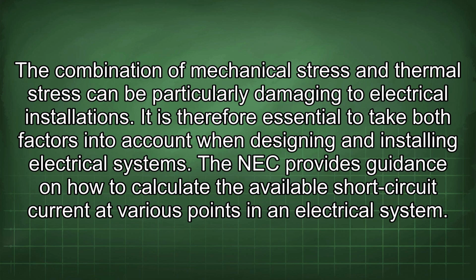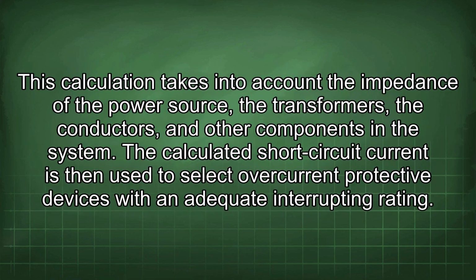The NEC provides guidance on how to calculate the available short-circuit current at various points in an electrical system. This calculation takes into account the impedance of the power source, the transformers, the conductors, and other components in the system. The calculated short-circuit current is then used to select overcurrent protective devices with an adequate interrupting rating.